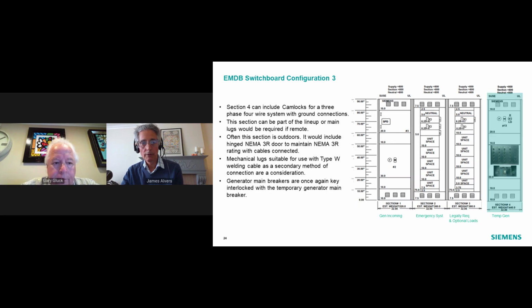Often it's outside, so it's NEMA 3R. There are covers over the cam locks so that when the temp generator is connected, it remains NEMA 3R rated. There are also options so that you can get lugs for type W welding cable as a secondary connection to a temp generator. Once again, main breakers are Kirk keyed. Once again, consider grounding.